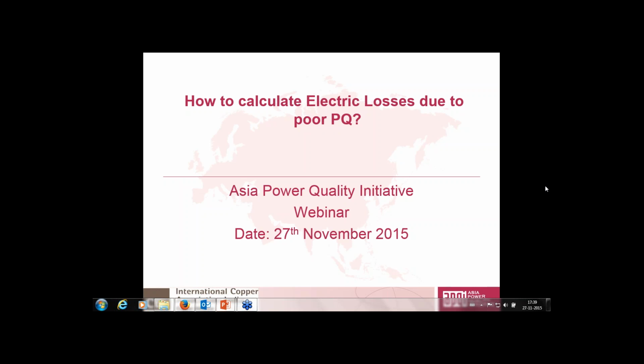The next question to you again. How can one calculate the average power factor of a three-phase unbalanced system? Well, the way we approach all of our calculations is that first of all we take instantaneous values, and we make our measurements in accordance with the IEC 61000-4-30 standard. That standard has been developed over quite a few years now, and it's essentially a guide to how you should make measurements and how you should represent them.